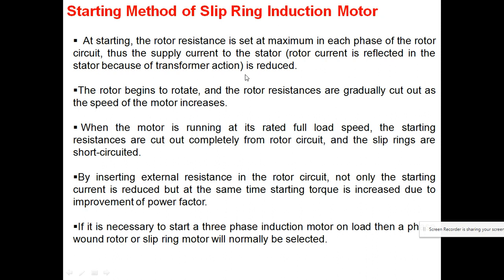Thus the current supplied to the stator is reduced. Why am I saying the stator current is reduced? Because I am working on the rotor. Due to the transformer phenomenon, our rotor current is reflected in the stator. That's why I am saying that when we put our rheostat at the high value, in that condition the supply current of the stator is reduced.